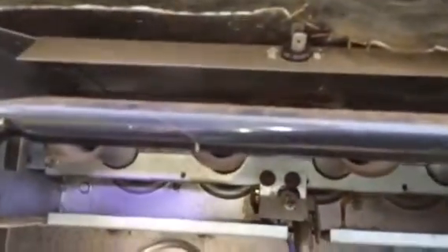This is my second trip out to this customer's house. This is a rental house. The first time I came out, the rollout switch had tripped. Where I have the camera pointed or focused is the rollout switch. This is a manual rollout switch.